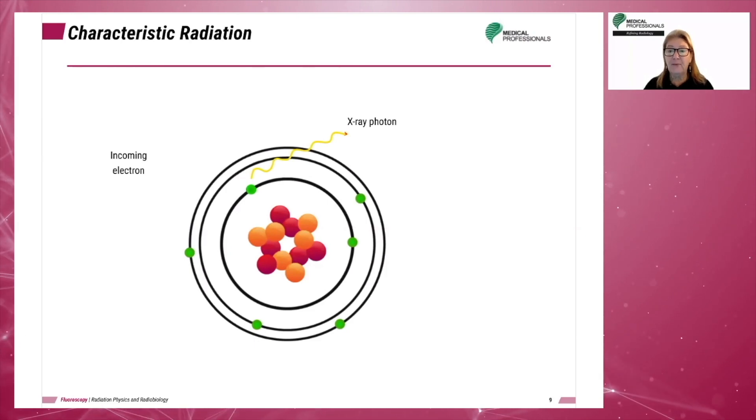Characteristic radiation comprises approximately 10% of the X-ray beam at the highest diagnostic range for kVp settings. The higher the kVp, the more characteristic radiation produced because there are more electrons of sufficient energy to produce characteristic radiation.